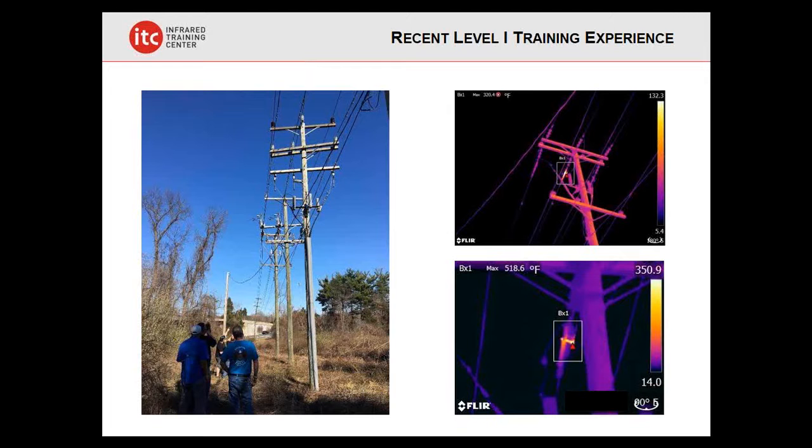I'm going to bring this back in a little bit later on here, but I want you to see those temperatures there. That's not a typo on the slide. At a minimum, this thing was hundreds of degrees warmer than what it should have been. In fact, we're seeing a max temperature here in the lower right side of over 500 degrees Fahrenheit.